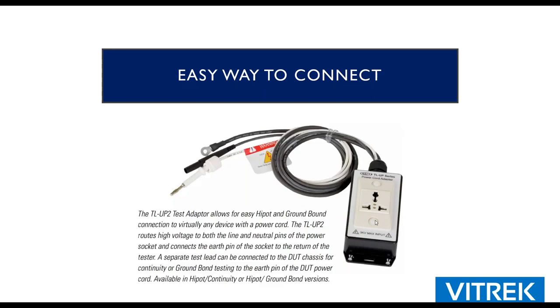All right, so back to the connections. So yes, you can take alligator clips and you can clip the alligator clip to line and neutral. You can clip another one to ground. That works. There's thousands of people out there doing it. We're totally guilty of doing it at the factory at Vitrek, although not in production, but for some testing and things like that. The downside there is you do have exposed high voltage, as well as inconsistencies in the contact between the alligator clips and the end of the power cord.